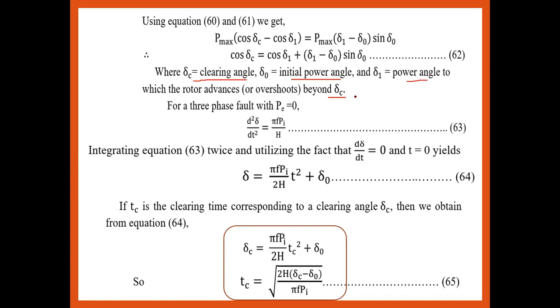For a three-phase fault, Pe equals zero, thus the swing equation becomes: d²δ/dt² equals π·f·Pi / H. Integrating this equation twice, we get the delta value as: delta equals (π·f·Pi / 2H) · t² plus delta-zero. If tc is the critical clearing time corresponding to the critical clearing angle, then from this condition we obtain the critical clearing time: tc equals √(2H·(delta-c minus delta-zero) / (π·f·Pi)).